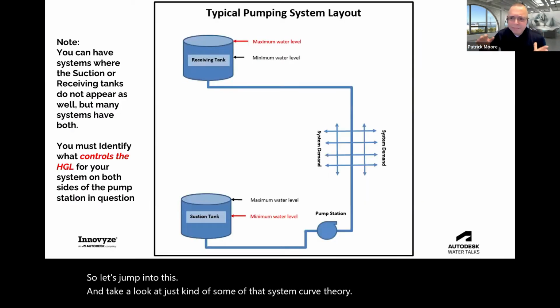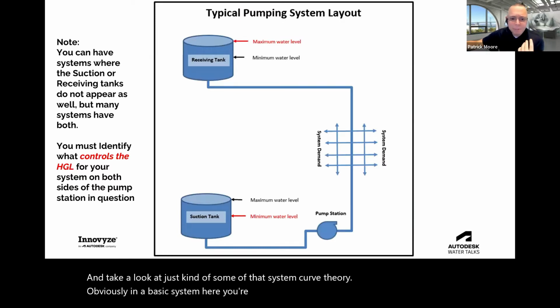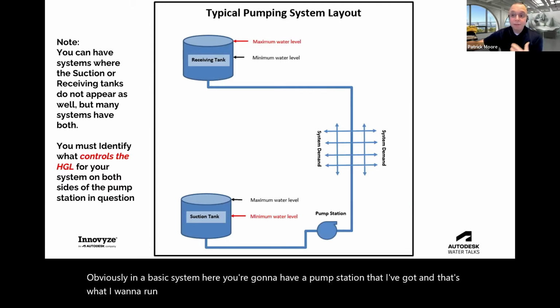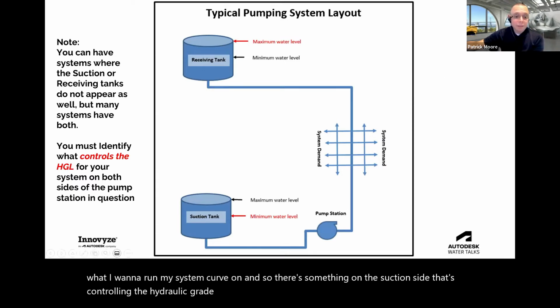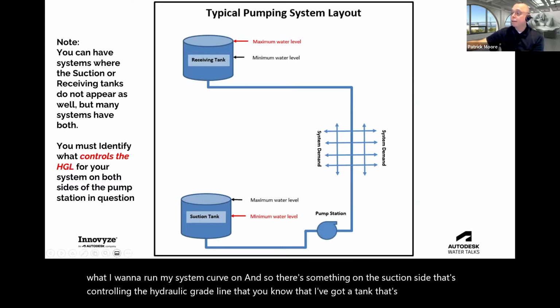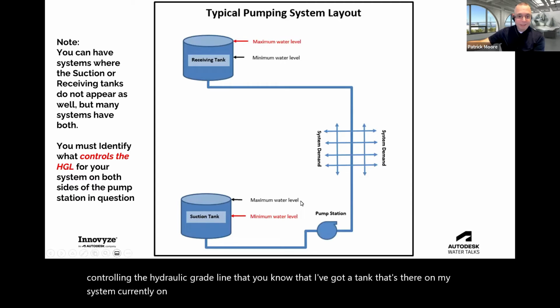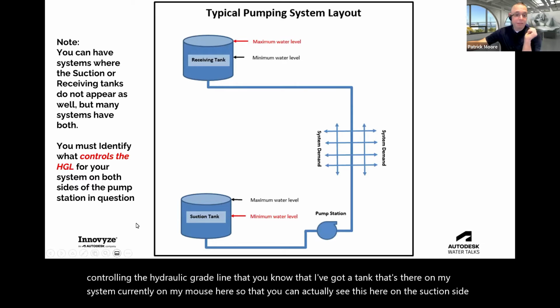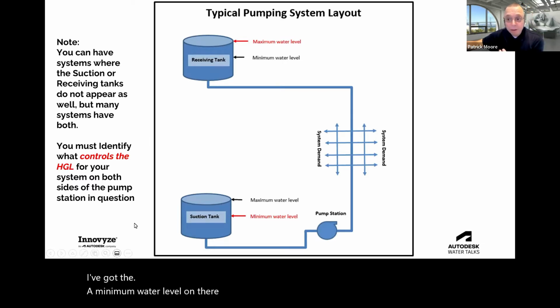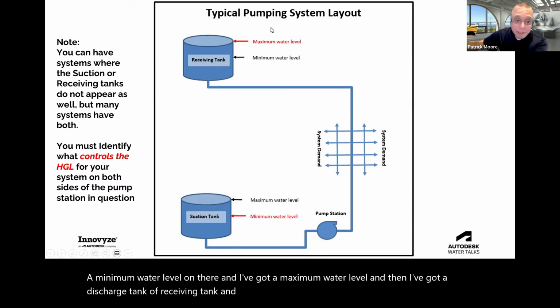Obviously in a basic system here, you're going to have a pump station that I've got, and that's what I want to run my system curve on. And so there's something on the suction side that's controlling the hydraulic grade line. I've got a tank that's there on my system curve. Let me find my mouse here so that you can actually see this. On the suction side, I've got the minimum water level, and I've got a maximum water level, and then I've got a discharge tank, a receiving tank, and that receiving tank has got a minimum and a maximum water level as well.